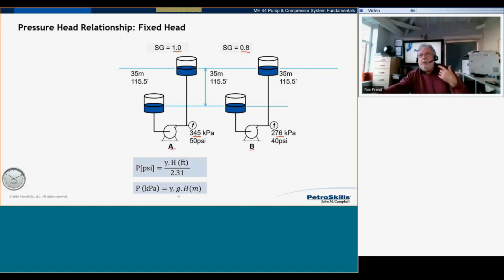Now remember, we're putting the same amount of specific energy in. That's kilojoules per kilogram or meters or feet, whatever you want to call it. But what we've got is for the same head, the pressure depends on the specific gravity. Now I've got a question for you guys. Which pump is moving the most flow?